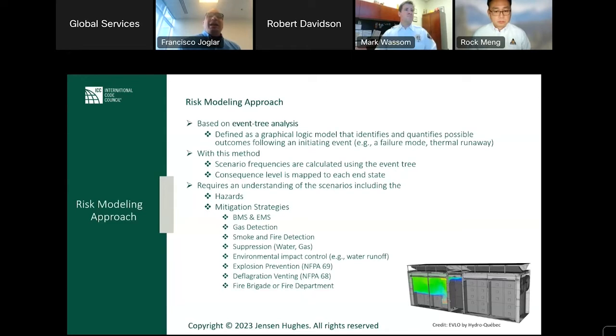So if I didn't detect gas and I detect fire, I am going to release my gas and not use the ventilation system so I can hold the concentration, and vice versa. If I detected gas, I may lock the suppression system so that I can vent the system. All of that has to be well understood and documented. Some cabinets have explosion prevention and venting, deflagration venting. And then it's what you are going to instruct your fire brigade or the fire department to do.